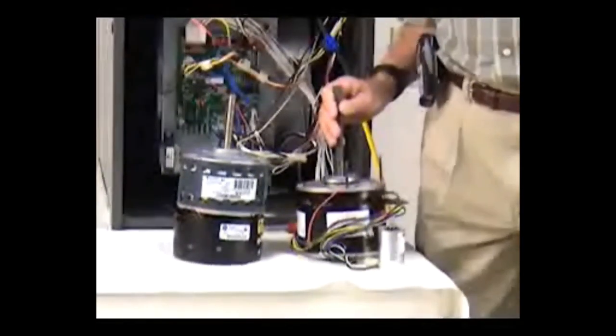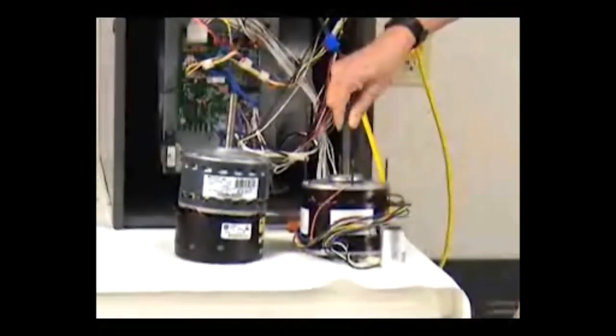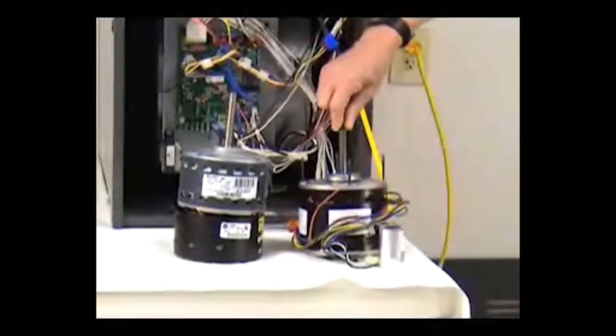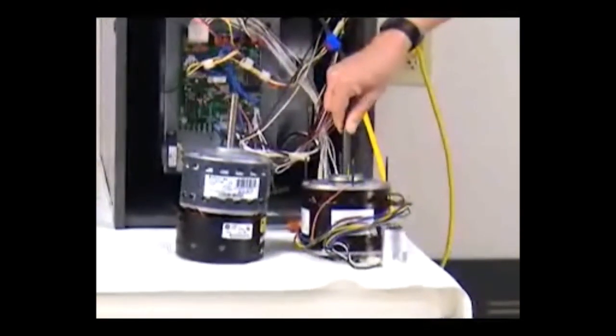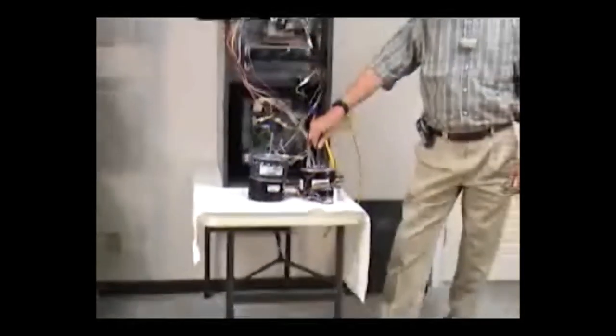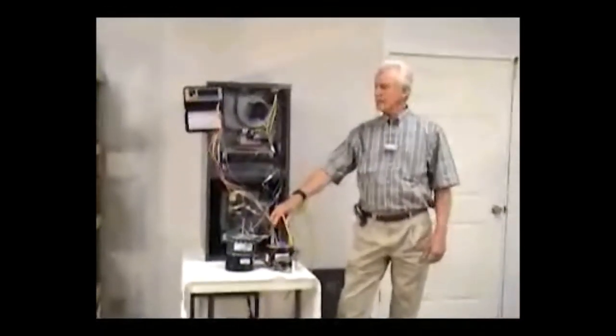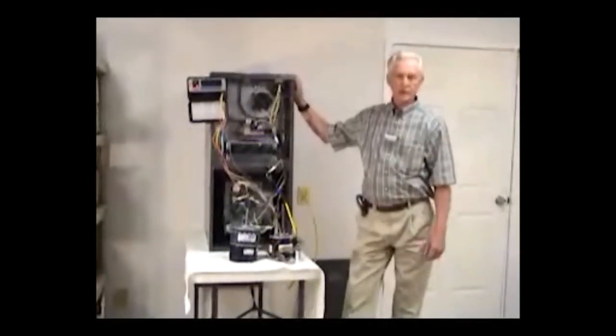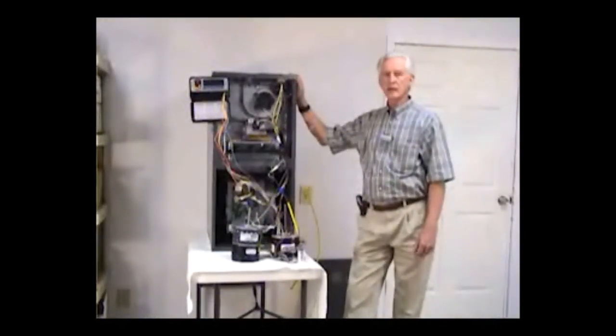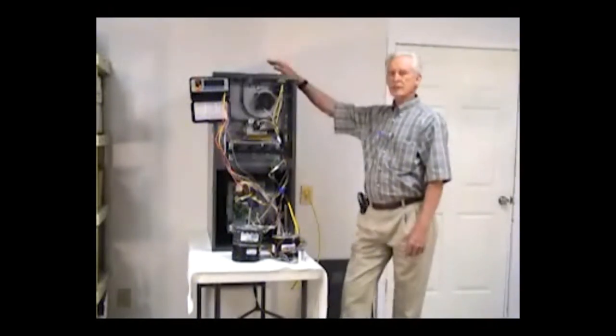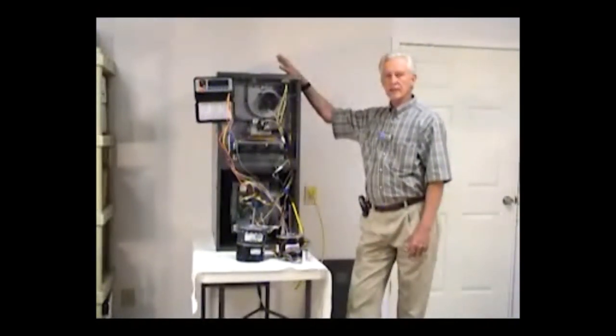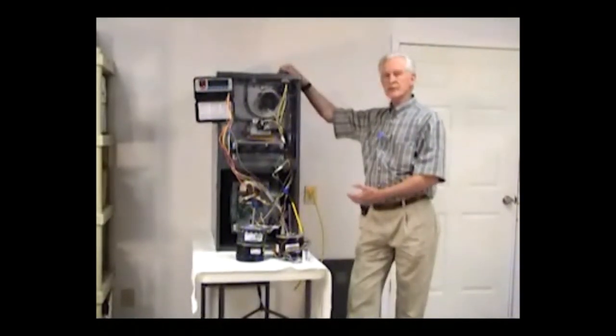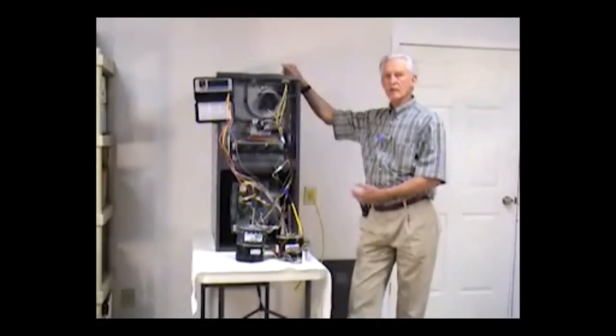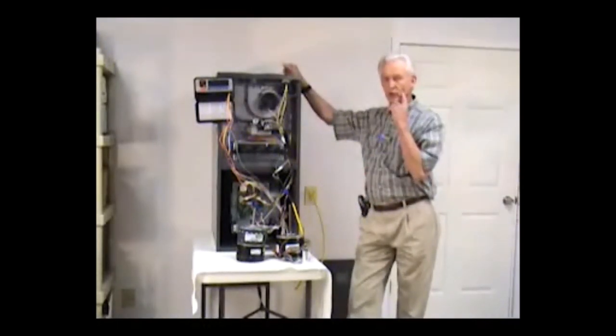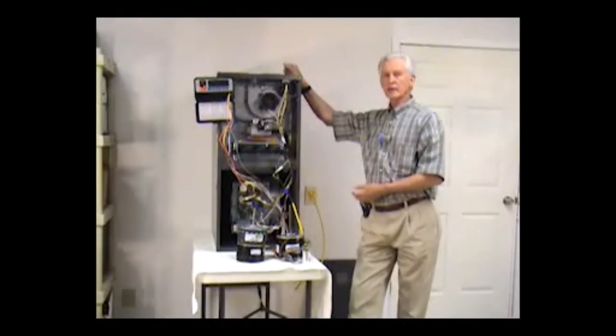What happens when you're dealing with a split capacitor or PSC motor is, lots of times we think in terms of a load that is being put against this motor, and that load being what happens when we turn a furnace on or turn the blower on and we are running air through the furnace, which is going to have usually a coil, air conditioning coil, ductwork on it, and in many cases, if they're installed in attics or locations where they have to remote the return, then we have ductwork on the return side.